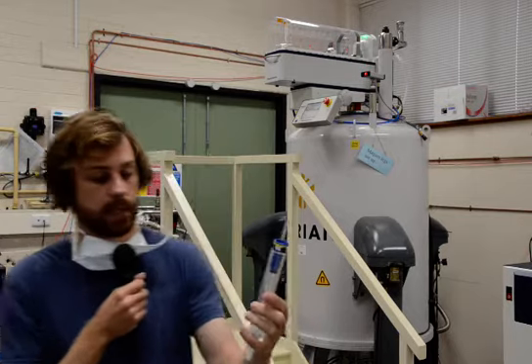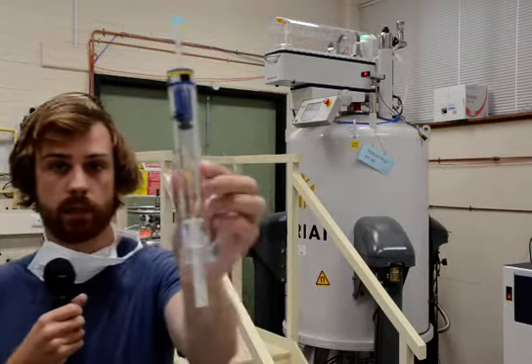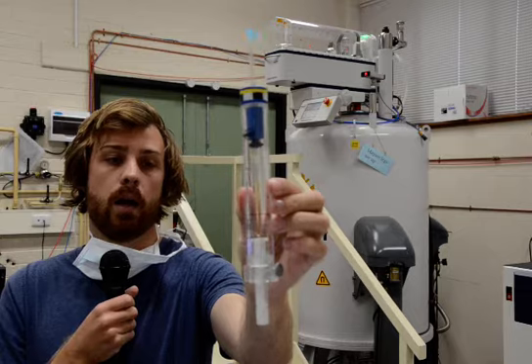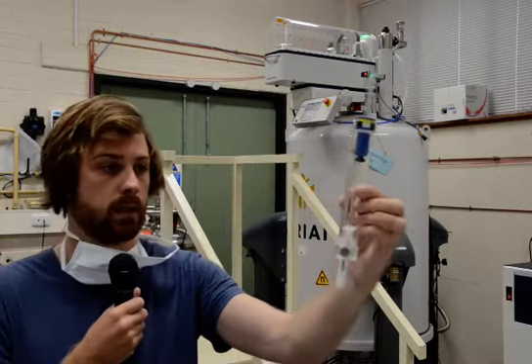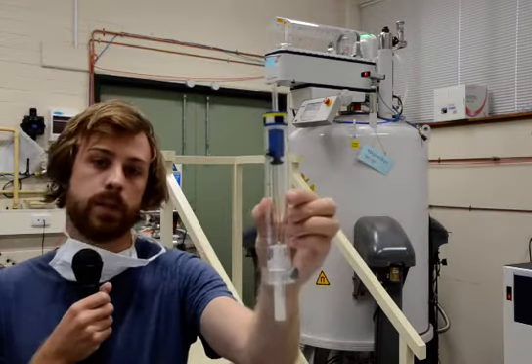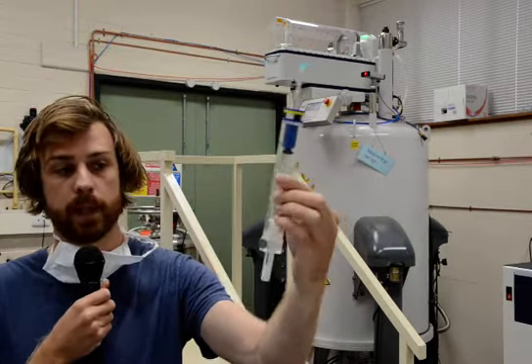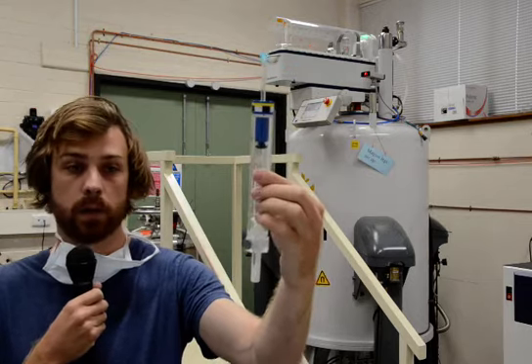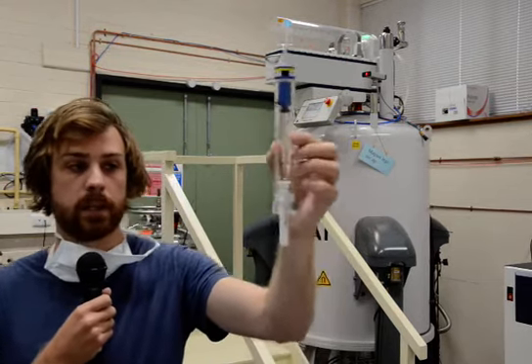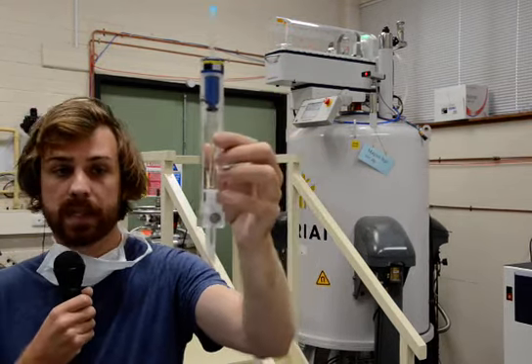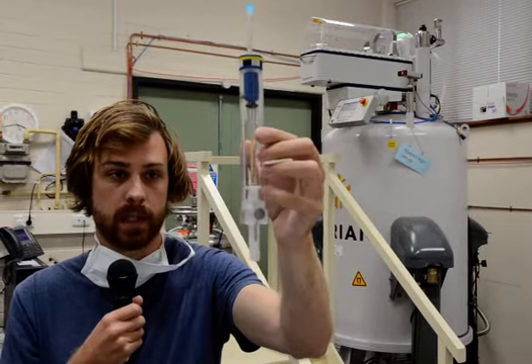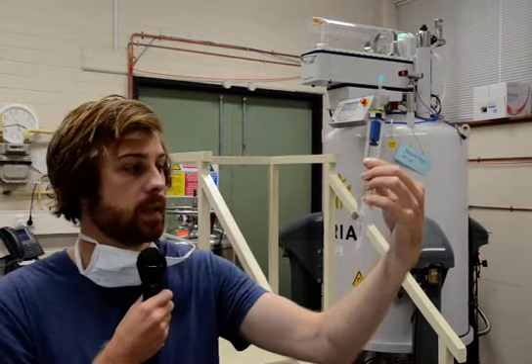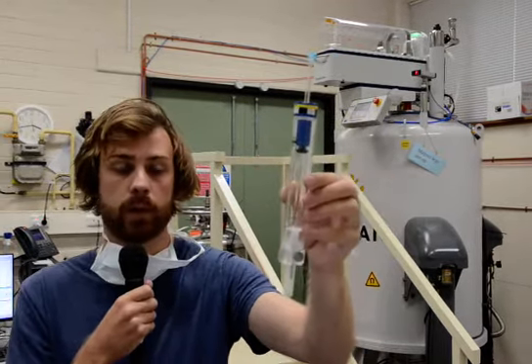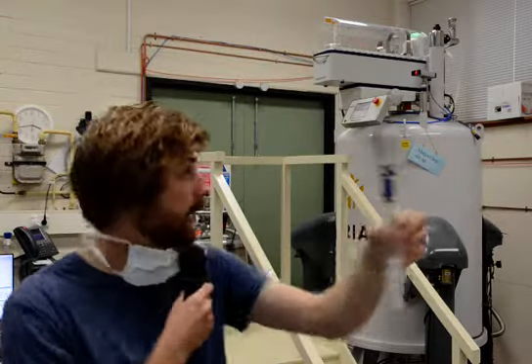What you'll notice on the gauge is there's two things. There's a nice little 10 millimeter line there, which is where the sample needs to reside. You need 10 millimeters of sample to acquire a good spectra. Any less or any more, and the spectra starts to get lower in quality. The other thing is you need to make sure the sample isn't touching the bottom of the plastic, you can see at the bottom where my pinky is. What's there is the bottom of the spectrometer, and obviously you wouldn't want your sample to go through the bottom of the spectrometer. As you can imagine, taking it apart to clean it is actually quite difficult.